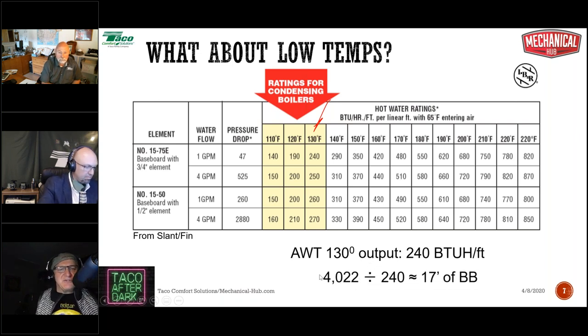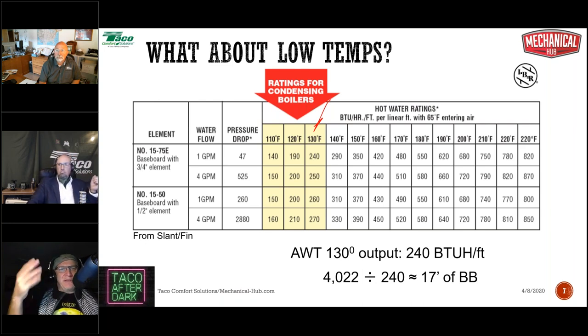Simple math, now 4,022 BTUs divided by 240 BTUs per foot. Now we're looking at about 17 feet of baseboard, a little bit more than double what we had before. 17 feet of baseboard in that room is not a big deal. All right, it's not a killer. We can certainly do that, and we can take advantage of the fact that we could put in a condensing boiler. The thing is, with baseboard, a lot of folks will automatically decide that if it's baseboard, it has to be 180 degrees. It won't work otherwise. So they don't even, in a remodel or rehab, think about a ModCon boiler.